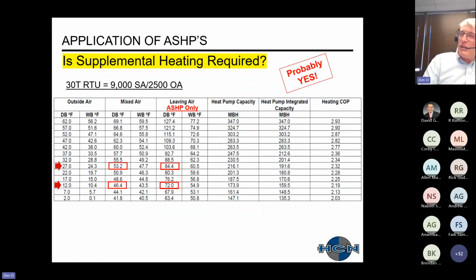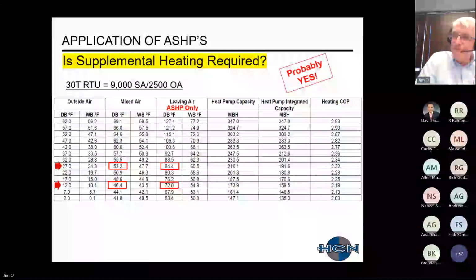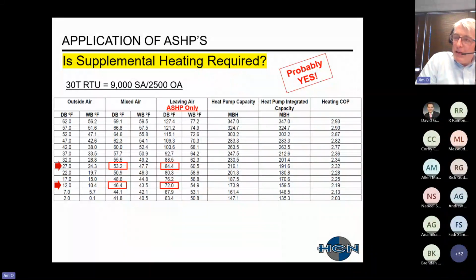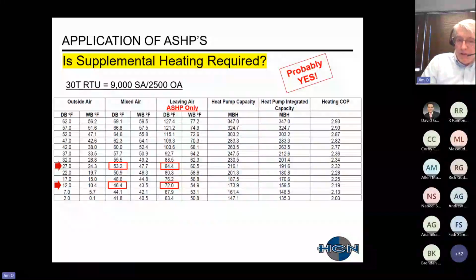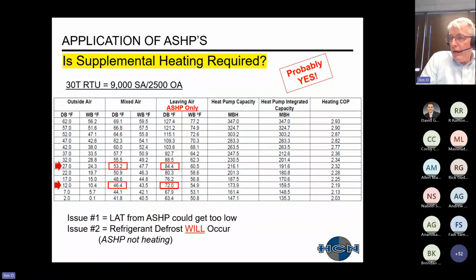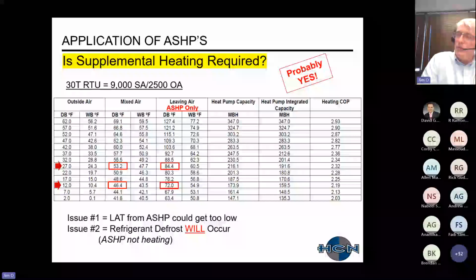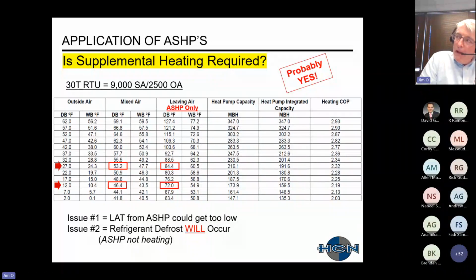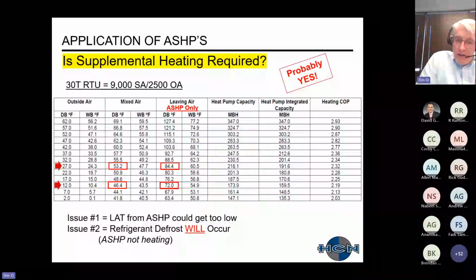All right. So once again, looking at as our temperature gets lower outside here, 27 and 12 degrees ambient. This is once again done for the Philly market that I primarily work in. You have our mixed air temperature at 53 and 46, and then you have a leaving air temperature at 84 versus 72. So issue number one is that our leaving air temperature could get too low. Say if it's 12 degrees out, we had a space at 75, we would want our leaving air temperature to be approximately 95. 72 degrees is going to be too low. And then issue number two that I'm going to further explain is that refrigerant defrost is going to occur.